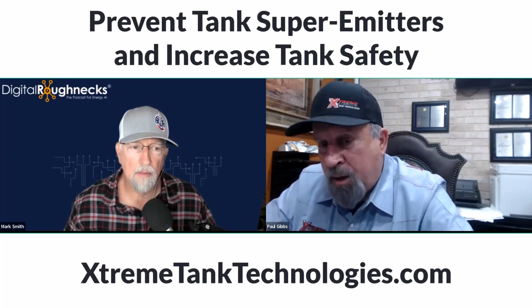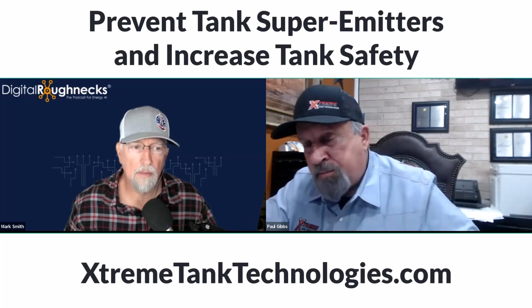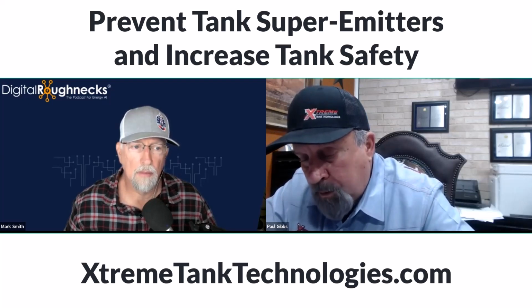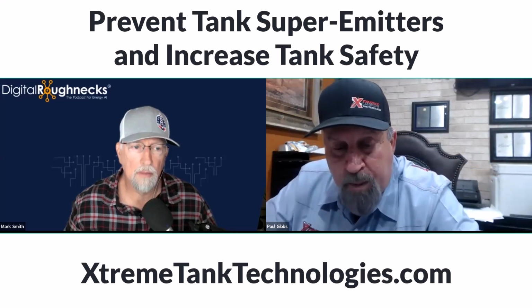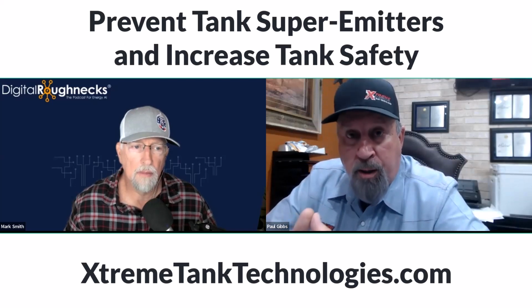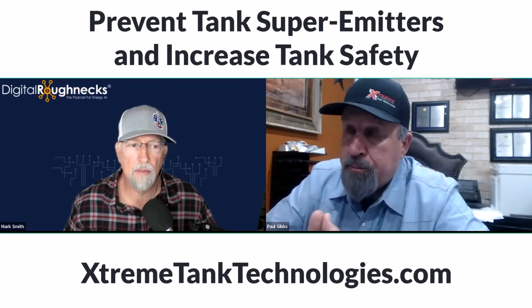And instead of removing any gases in the saltwater disposal business, we will put gas in. We'll take gas from the tank battery. We will release it with my tool at the surface of the level, and we will remove it off the roof through the traditional way. But by doing that, we're sweeping the tank, making sure there's no oxygen in there. The difference between a tank fire and a tank explosion is oxygen.